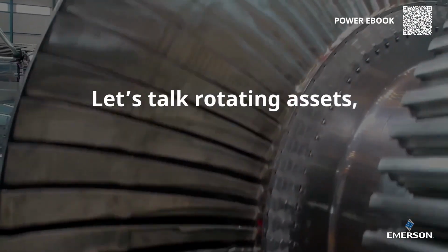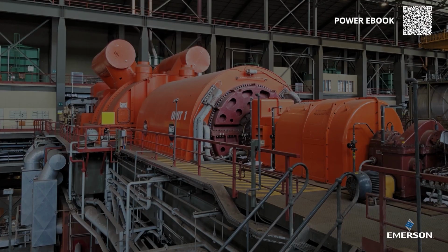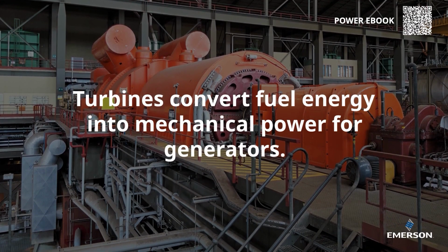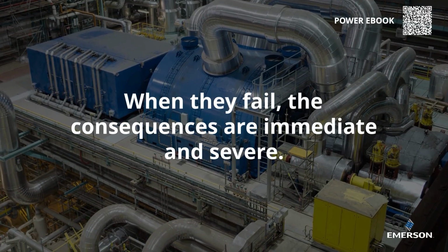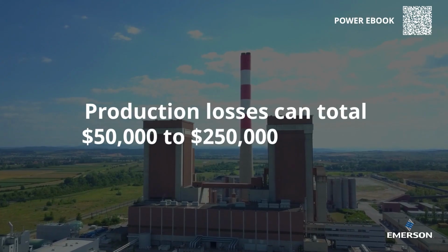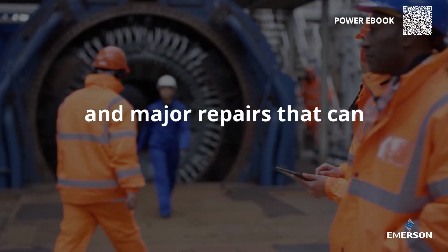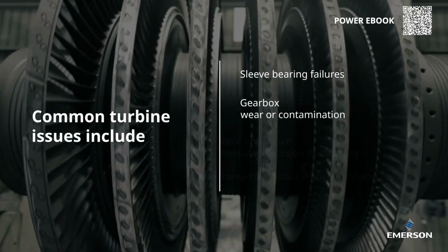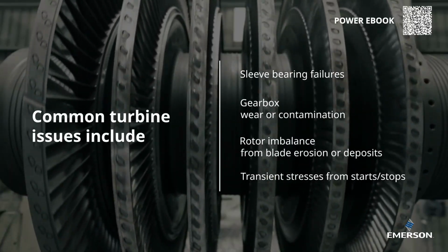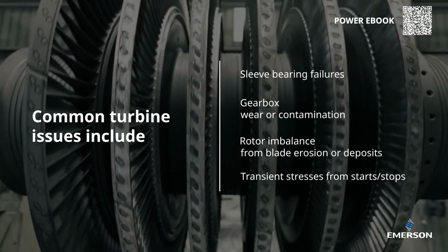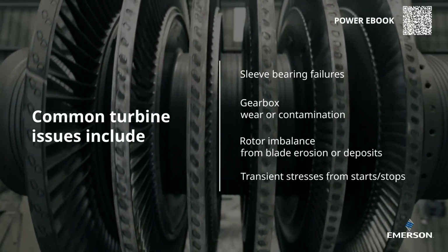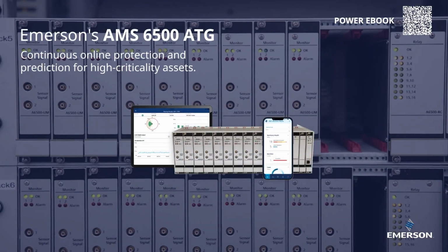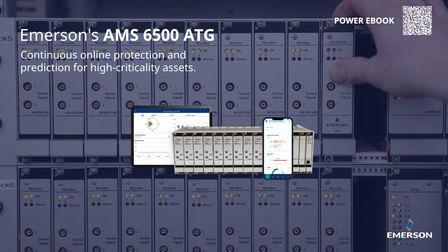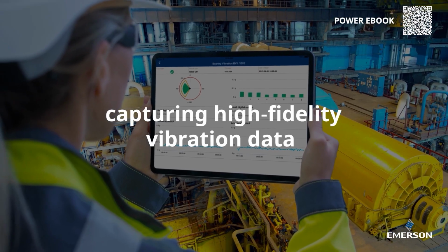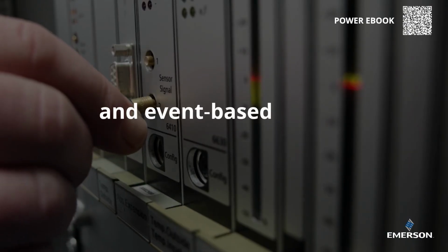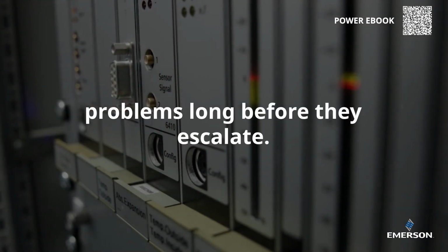Let's talk rotating assets, starting with the heart of the plant, turbines. Turbines convert fuel energy into mechanical power for generators. When they fail, the consequences are immediate and severe. Production losses can total $50,000 to $250,000 per day, and major repairs can exceed $10 million. Common turbine issues include sleeve bearing failures, gearbox wear or contamination, rotor imbalance from blade erosion or deposits, and transient stresses caused by frequent starts and stops. Emerson's AMS 6500 ATG provides continuous online protection and prediction, capturing high-fidelity vibration data, PeakVue impact detection, and event-based flight recorder insights to catch problems long before they escalate.